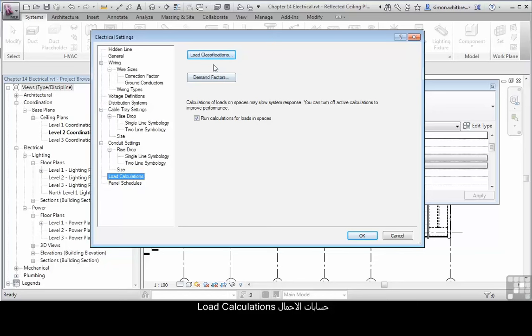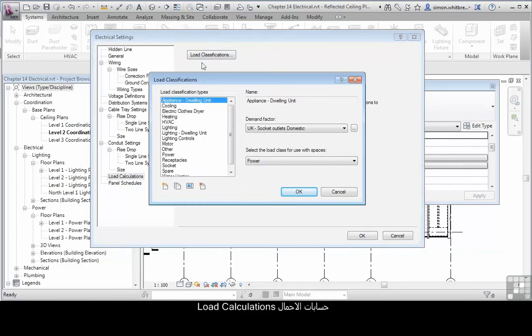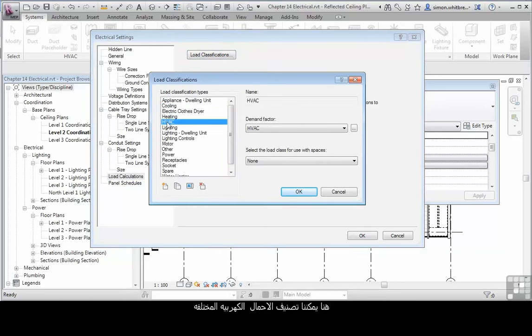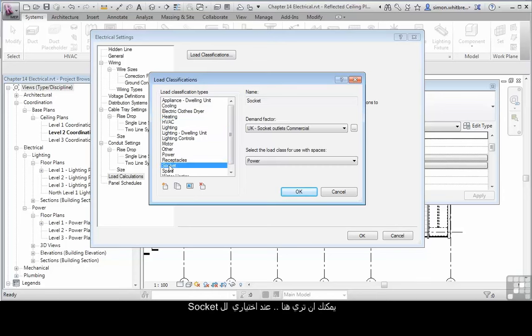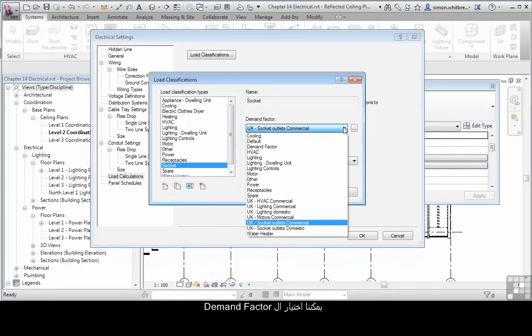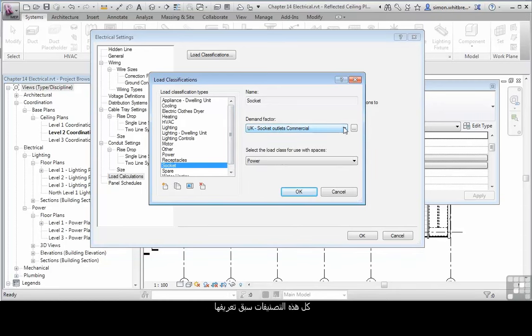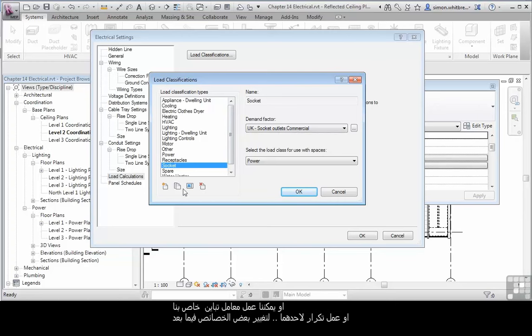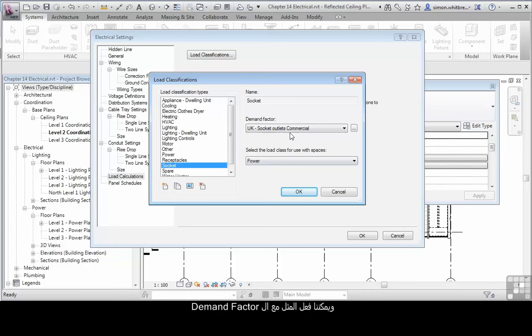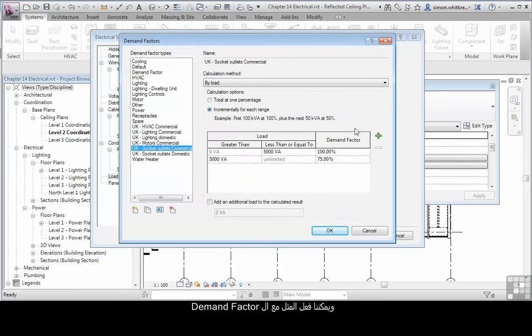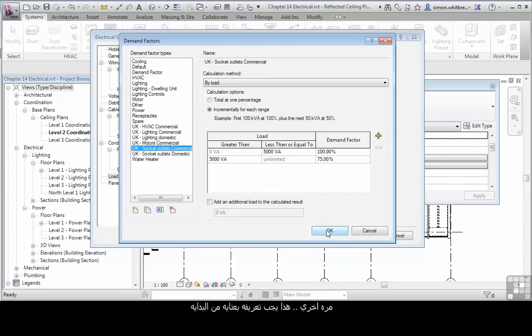Load calculations. Here we can define load classifications for different types of electrical loads. Here you can see where I select socket, we can choose a type of demand factor. These are fully customizable. We can create our own, duplicate them for an existing. And for the demand factor, we can do the same. Once again, this needs to be carefully set up at the outset.